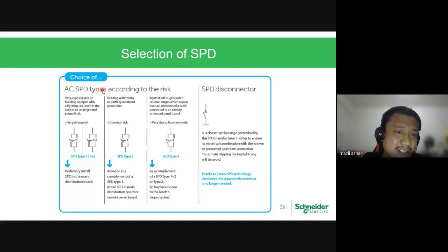So how to select? Okay, for very strong risk, type 1 or type 1+2 is for an exposed area where the building is equipped with a lightning rod, as I mentioned, with a lightning rod. Okay, and then if the building has totally or partially overhead power lines or has pylons, okay, so you need to put type 2. Normally you can see in a big urban residential area that we need to install a type 2 SPD. And then if a self-generated surge goes to the sensitive equipment, then you need to put a type 3 SPD.